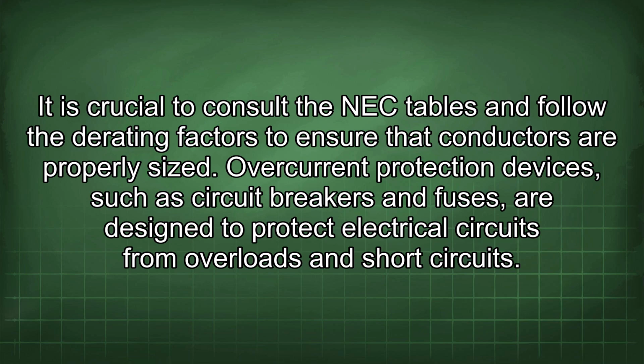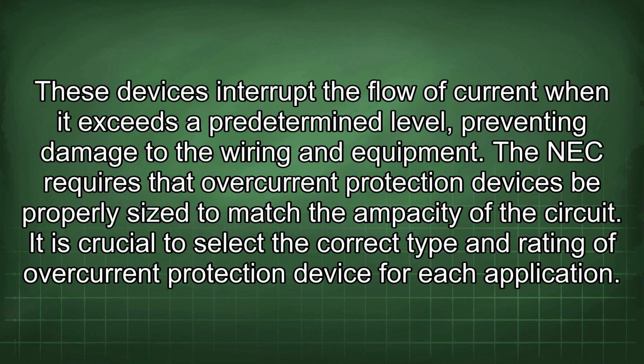Overcurrent protection devices, such as circuit breakers and fuses, are designed to protect electrical circuits from overloads and short circuits. These devices interrupt the flow of current when it exceeds a predetermined level, preventing damage to the wiring and equipment. The NEC requires that overcurrent protection devices be properly sized to match the ampacity of the circuit. It is crucial to select the correct type and rating of overcurrent protection device for each application.